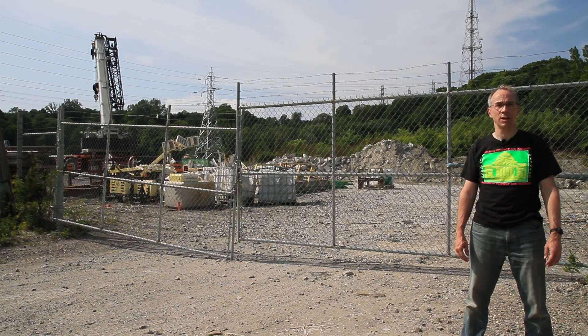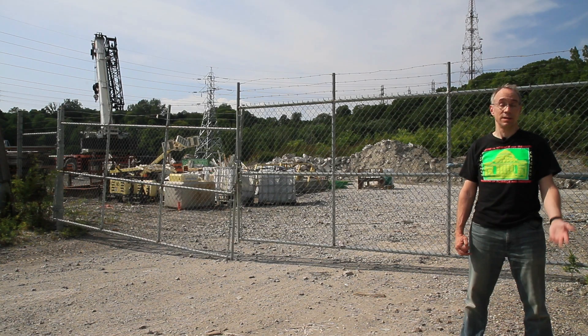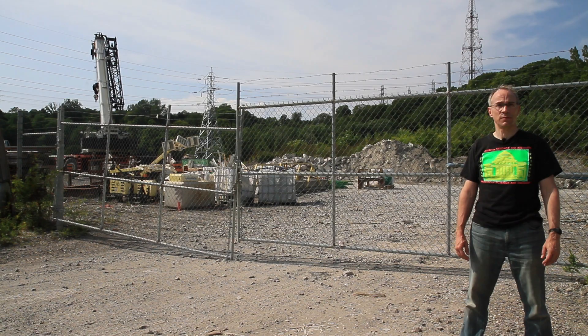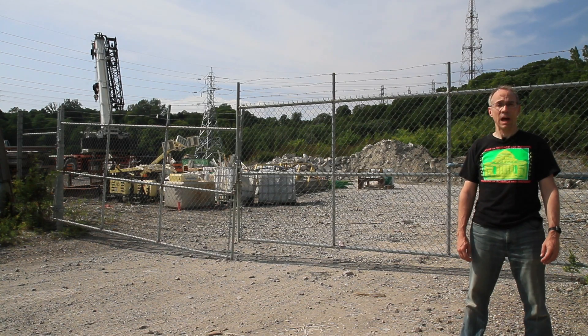It's not really practical to fix this by ripping up large parts of the old city and replacing the combined sewer system with two separate sewer systems. So instead, the city has a project that's been underway for the last decade or so to improve its ability to handle the excess flow. Right next door to the sewage treatment plant we just visited, they're building a large underground tank into which the excess flow will be diverted at times of high flow. Some of the solids settle out and the water that's left, while still dirty, at least doesn't have the solids in it. It will get pumped to a separate high-volume treatment facility located near Ashbridges Bay, which will disinfect it with UV light before letting it out into the same outfall pipe as the outfall from the main sewage treatment plant, which will then disperse it through a series of nozzles at the bottom of Lake Ontario a few kilometers out into the lake. So it's not fully treated, but at least it's not a biohazard and it's dispersed well out into the lake. That's going to help a lot. I hope you've enjoyed this video — please like and subscribe.